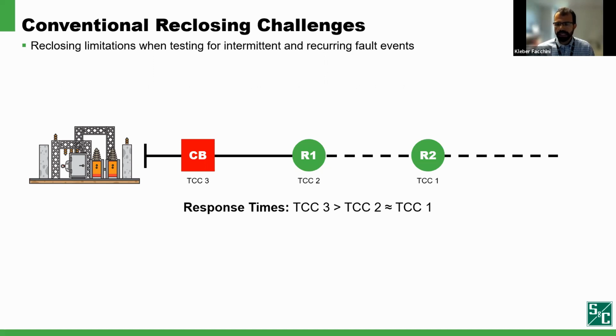This may eventually lead to the upstream recloser lockout, creating unnecessary outages to more customers in the feeder. In this scenario, besides voltage sags introduced in the system by repetitive reclosing, reliability has also been affected, as now all customers downstream of the R1 recloser will see a prolonged outage.